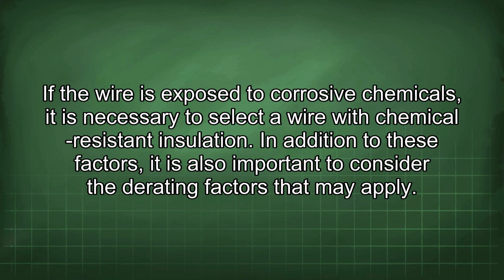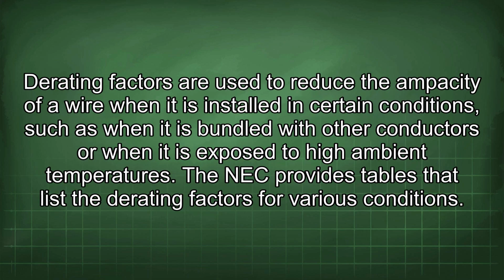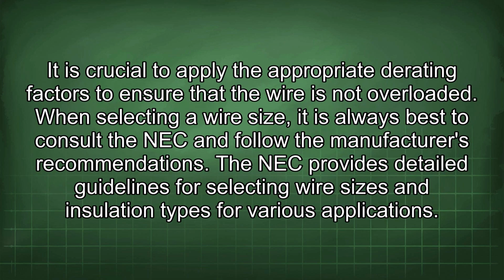In addition to these factors, it is also important to consider the derating factors that may apply. Derating factors are used to reduce the ampacity of a wire when it is installed in certain conditions, such as when it is bundled with other conductors or when it is exposed to high ambient temperatures. The NEC provides tables that list the derating factors for various conditions. It is crucial to apply the appropriate derating factors to ensure that the wire is not overloaded.